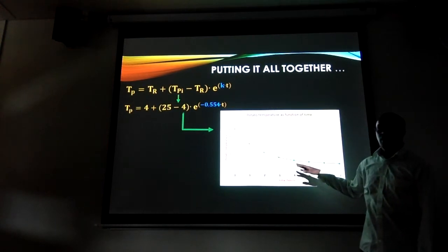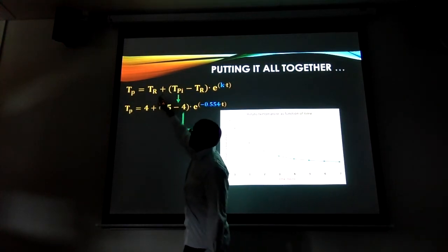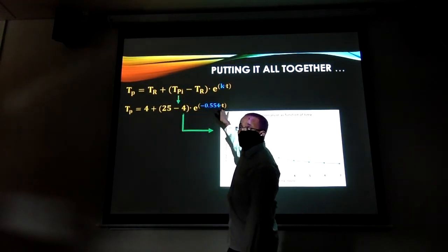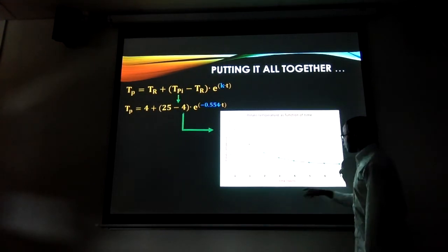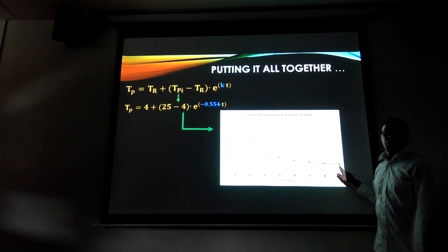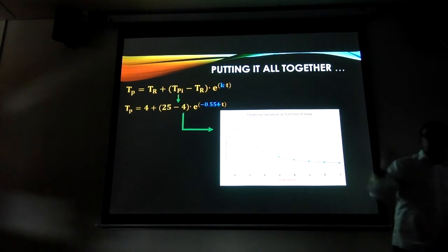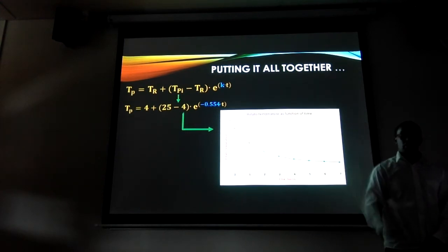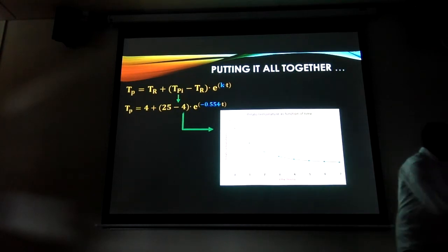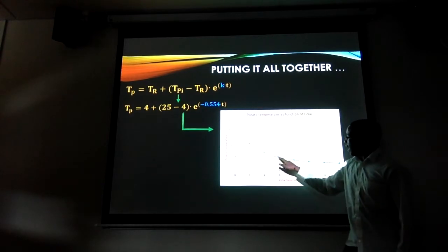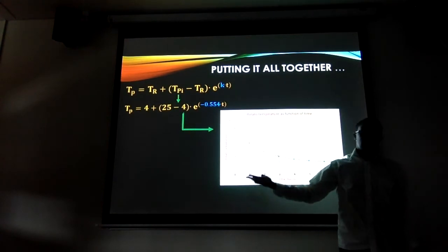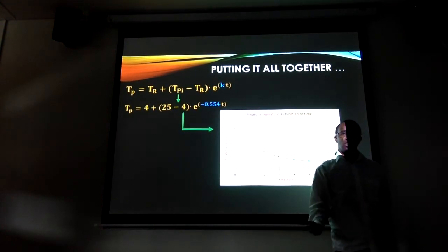as the time varies, right? So these are fixed, right? The room temperature is fixed, the initial product temperature is fixed. Only the thing that varies is time, right? So as we plot, as the time goes on, the product temperature goes down, and it attenuates towards the room temperature. Okay, so say the product temperature that's required is 5 degrees. So say after 3 hours, you want to check whether it has reached 5 degrees. So you just go to your 3 hours and you read across your temperature. It's about 8 degrees, so it's not good enough. Okay? So that's how you use it. So here is its usefulness.